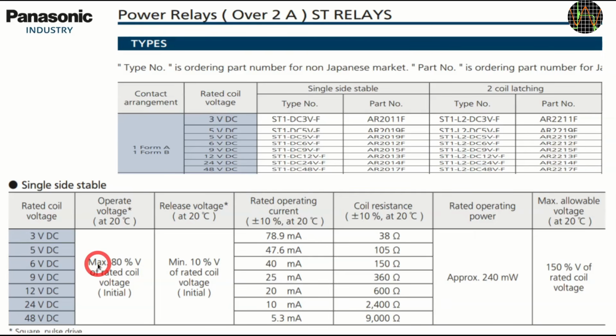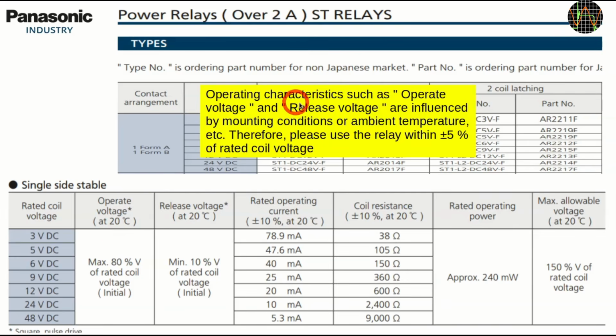The voltage may drop to the minimum release voltage, which in our case is 1.2 volts, before the relay disengages, but of course it might also happen at higher release voltages. The word initial in the datasheet means those specs are only true when the relays are brand new. Also, the operating and release is assumed to be square pulses, again something not the case here. Lastly, there is this statement regarding that the operating and release voltages are influenced by mounting conditions and temperature. All in all, this means that the calibration of this tester has to be repeated every so often because the thresholds of when the relays close or open will change over time and temperature.